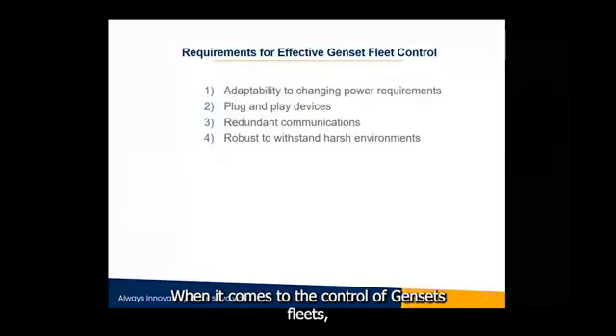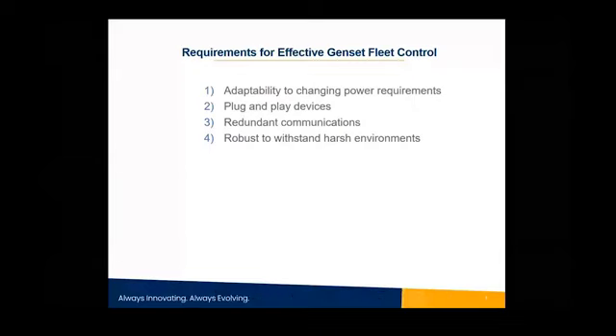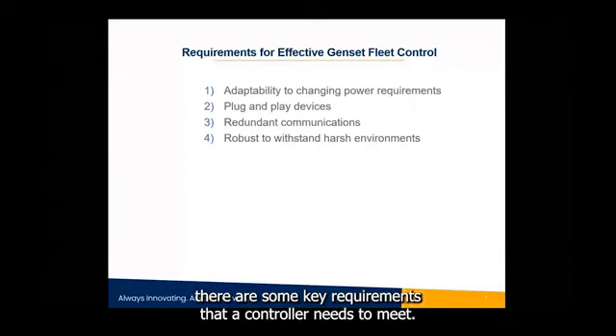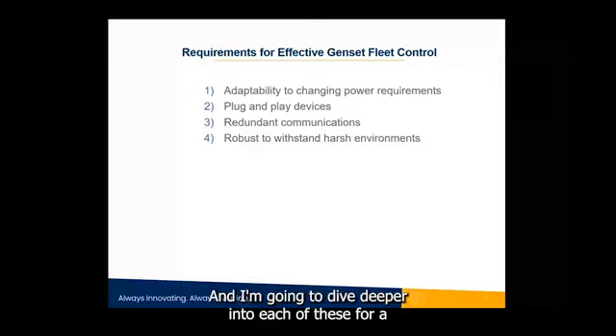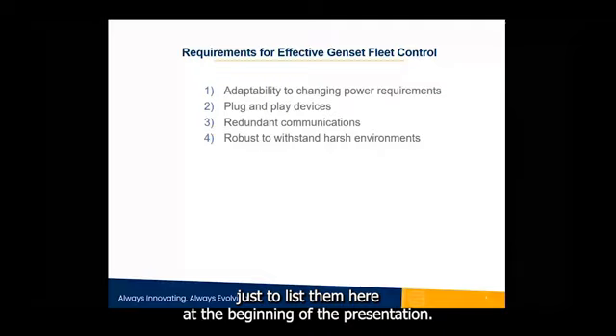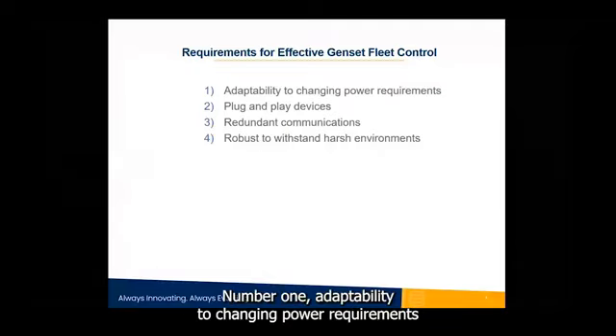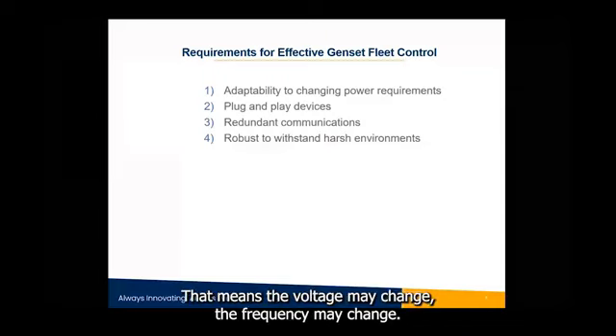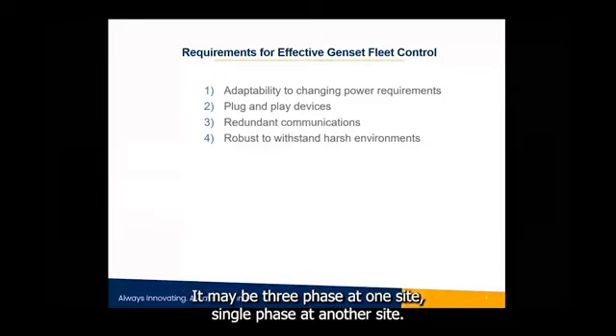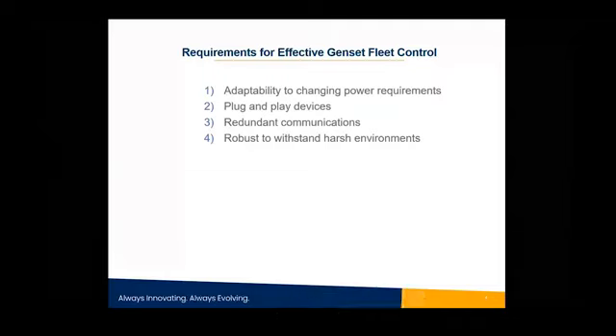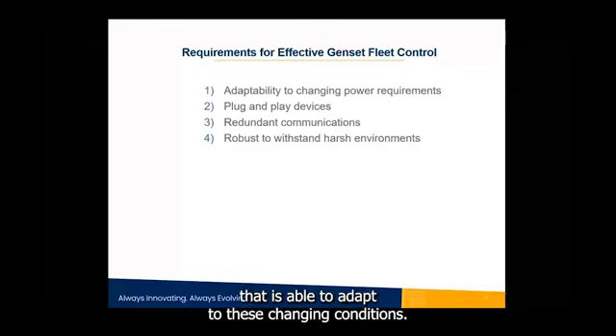When it comes to the control of genset fleets, there are some key requirements that a controller needs to meet. I'm going to dive deeper into each of these four, but just to list them here at the beginning of the presentation. Number one, adaptability to changing power requirements. As generators are moved from one site to another, the power requirements change. That means the voltage may change, the frequency may change. It may be three-phase at one site, single-phase at another site. And it is important to have a controller that is able to adapt to these changing conditions. Also, the ability to be plug and play.